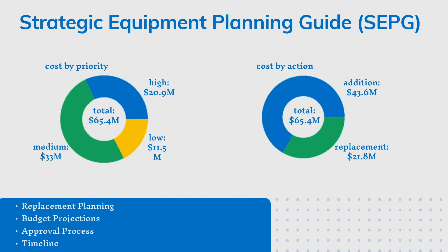The next phase is planning, specifically VA-specific planning requirements for equipment, starting with the SEPG — the Strategic Equipment Planning Guide. This is the portal used for clinical services to input their equipment requests. From a clinical engineering perspective, we first do a full inventory audit for our assigned services distributed throughout the engineers. We go through that list, look for anything end of life, approaching end of life, or in poor condition, and then meet with the corresponding BESS team — imaging or critical care — to get their advice and make sure we encompass all of the need.